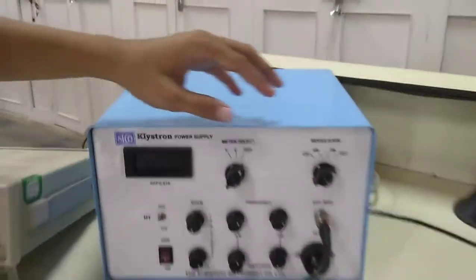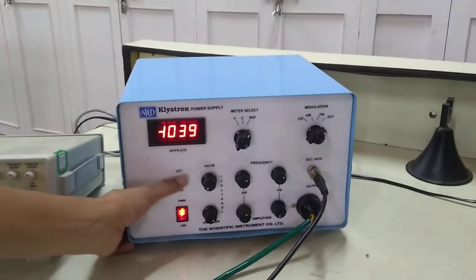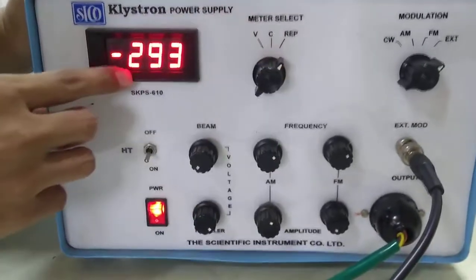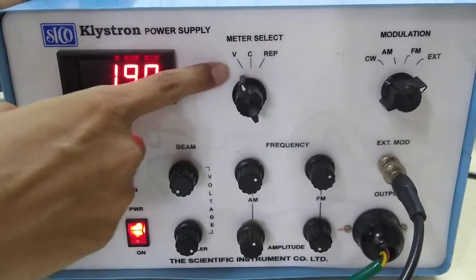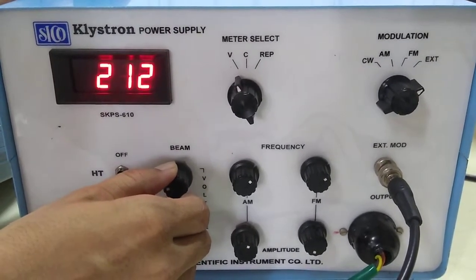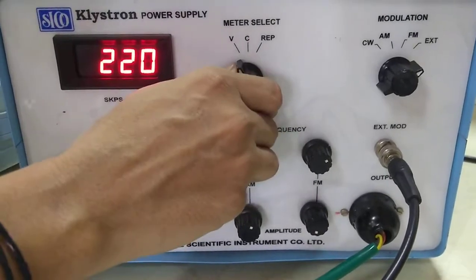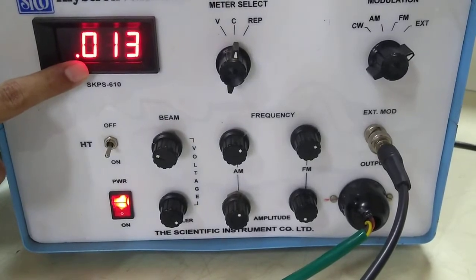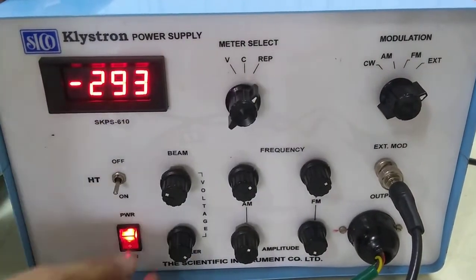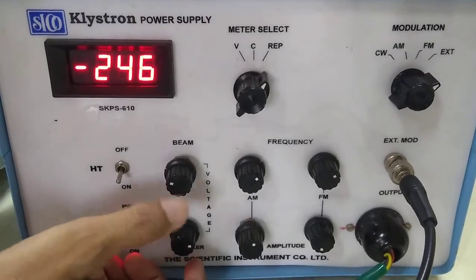You can switch on from mains and ensure that your cooling fan is on, which will protect your reflex klystron tube from overheating. Now you can switch on the power. On the display, there is a meter select knob: if it is on REP the display will show the repeller voltage, and if you take it to the voltage position it will display the beam voltage. As I increase the beam voltage you can clearly see the voltage is increasing — I will keep it at 220 volts. If you take the meter select to the current position it will display the beam current, which is 13 mA. The repeller voltage can be varied using the repeller voltage knob. The meter select knob gives you beam voltage, repeller voltage, and beam current on the display.